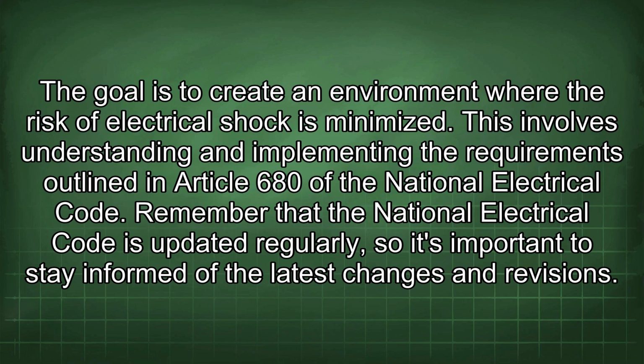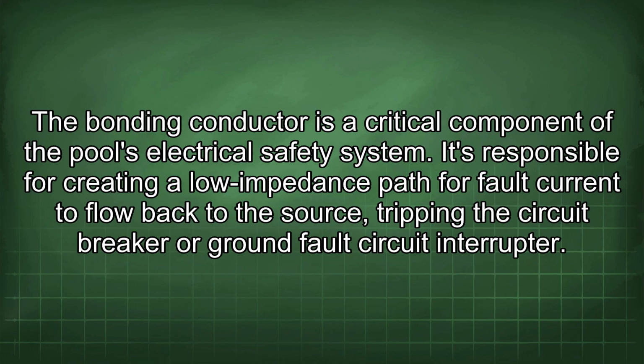The goal is to create an environment where the risk of electrical shock is minimized. This involves understanding and implementing the requirements outlined in Article 680 of the National Electrical Code. Remember that the National Electrical Code is updated regularly, so it's important to stay informed of the latest changes and revisions. The bonding conductor is a critical component of the pool's electrical safety system. It's responsible for creating a low impedance path for fault current to flow back to the source, tripping the circuit breaker or ground fault circuit interrupter.